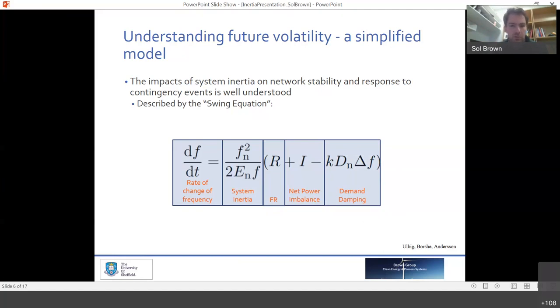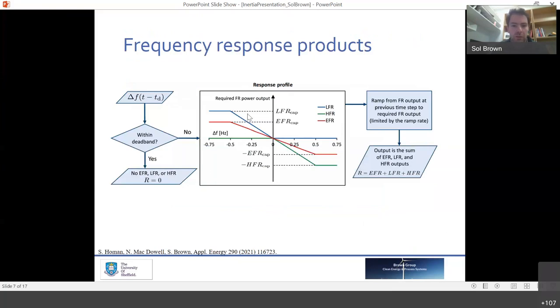So we use this simple method and ally that with an understanding of the existing frequency response products. This is a vague outline of the frequency response products that were available through National Grid before they deployed their new dynamic containment product. So you can see there's high and low and very fast acting enhanced frequency response, and then different types of frequency response with their different characteristics. We can use this as a means of pushing through the system's reaction based on the procured amount of frequency response, push that through the swing equation, and we can see how a system reacts both in largest infeed loss and ongoing frequency control.